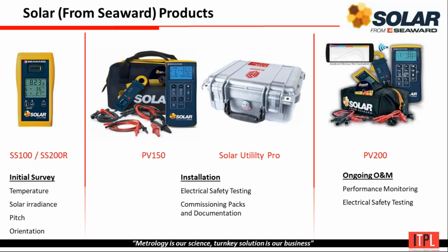The second one is the PV150. It's a normal array tester, as we can test a single panel or a complete string. Parameters like open circuit voltage, short circuit current, earth continuity, insulation resistance, string current and power - all these parameters we can get from the PV150 equipment. This we are supplying here in India and neighboring countries, and also in the Gulf countries.